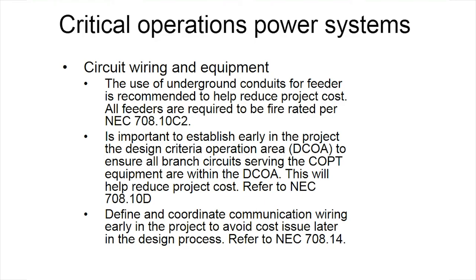Couple of tips on that. You don't need to have the break room. You don't need to have lobbies. Any of that stuff doesn't need to be part of the DCOA. If you plan your facility properly, you're not going to have this issue. You will be able to remove those areas and create two areas, the critical area and the non-critical area. That's good advice.